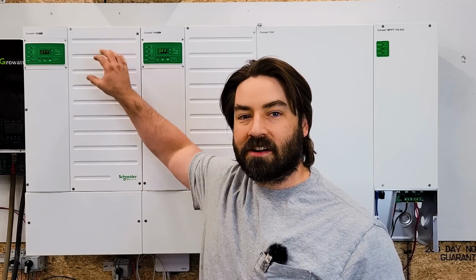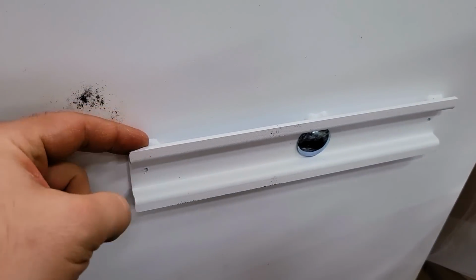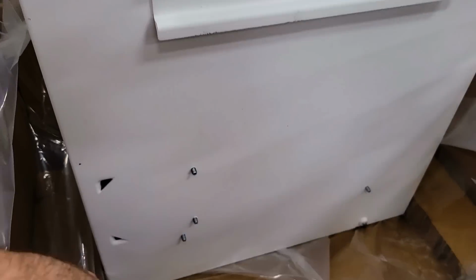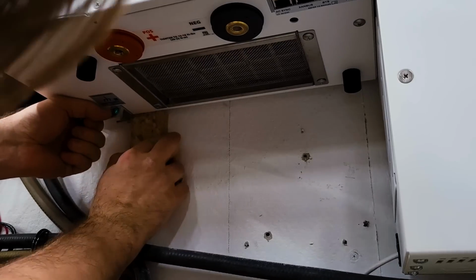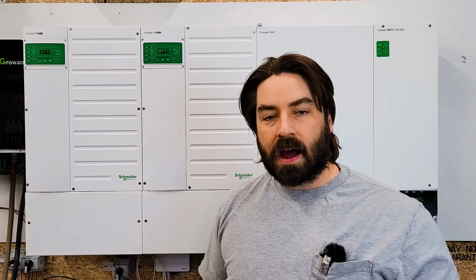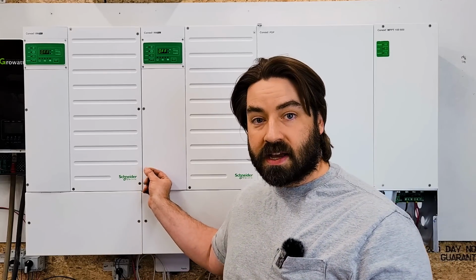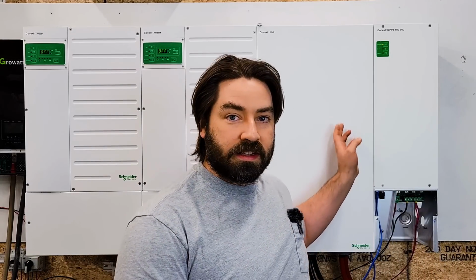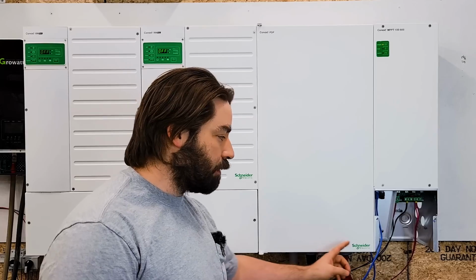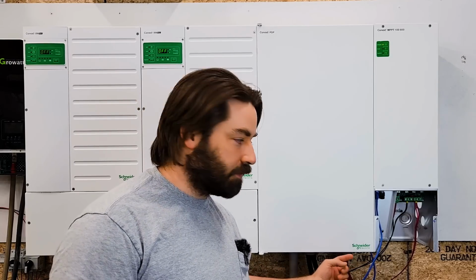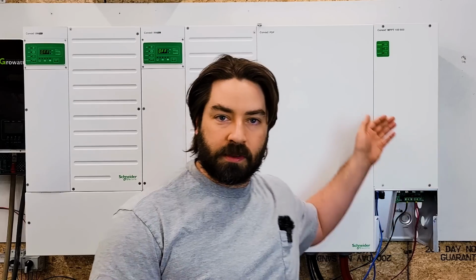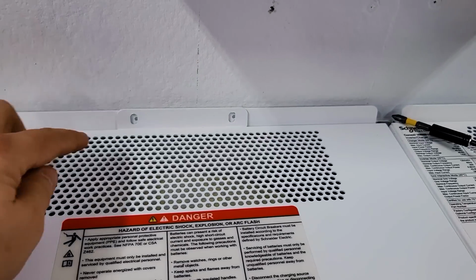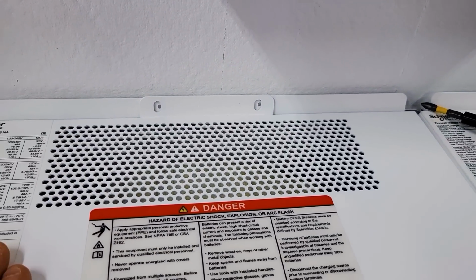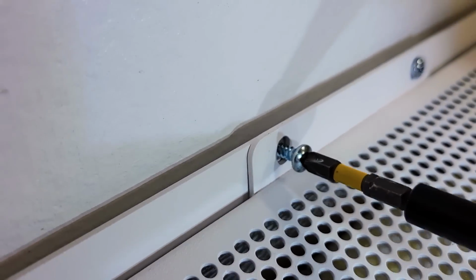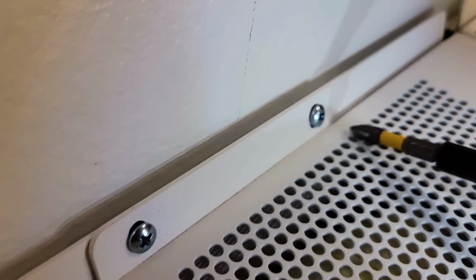And once you get it on there, it just hooks on that wall bracket and can hang there and wait until you get it situated. I actually added a couple of shims behind it because the inverter wants to tilt towards the wall at the bottom. I wish that Schneider would add a couple little standoffs behind there, just like they did on this PDP. The PDP came with a couple of plastic standoffs in the bottom 2 corners that keep the PDP plumb. The top is secured with a couple of number 10 screws that come with it. That keeps it from, if you hit this thing, bouncing off and coming off that bracket.